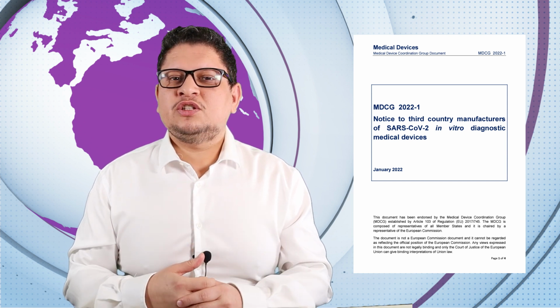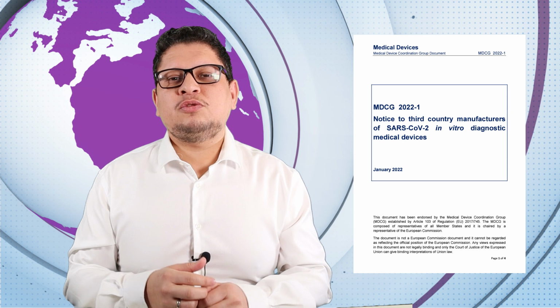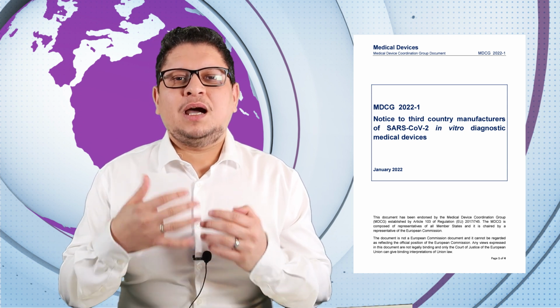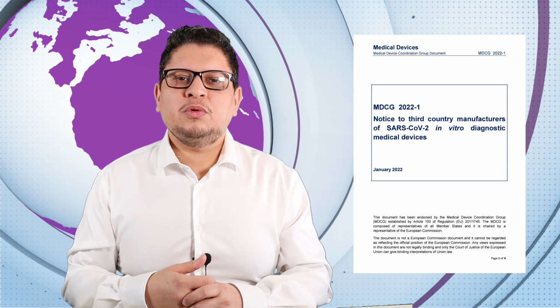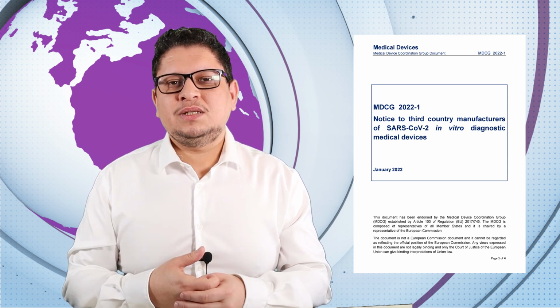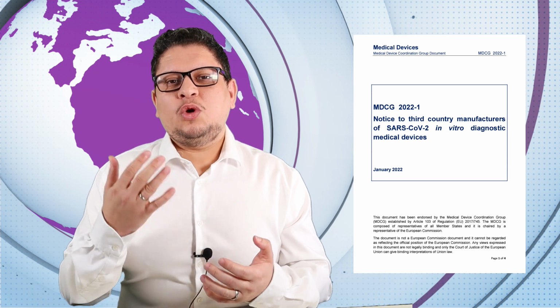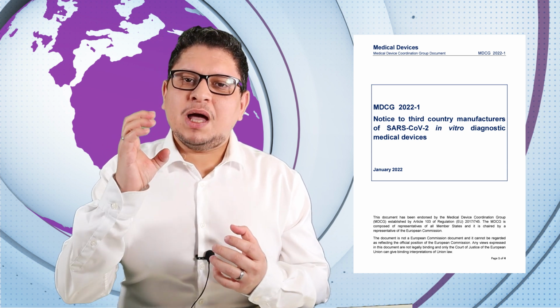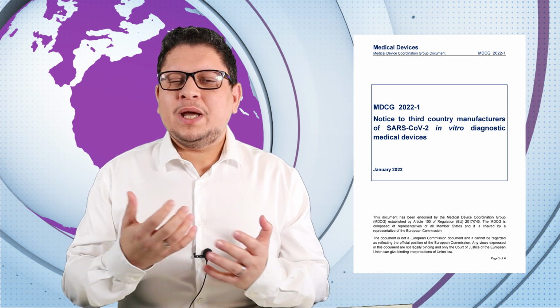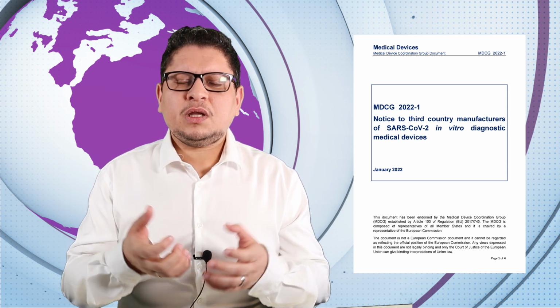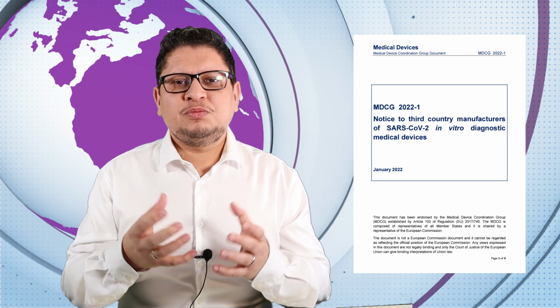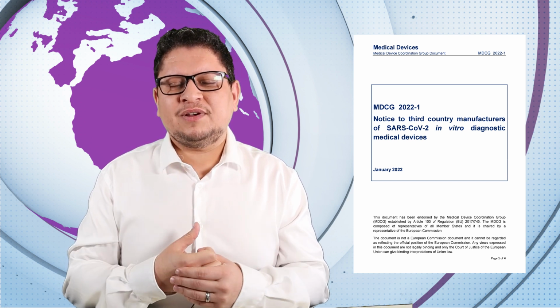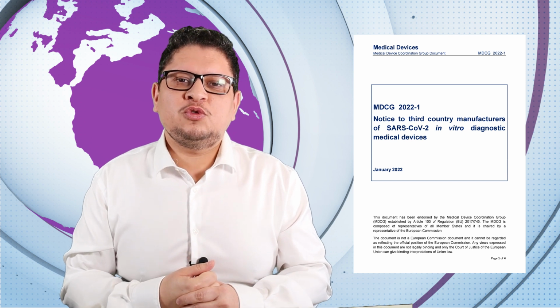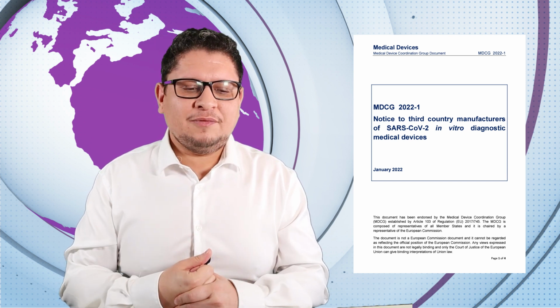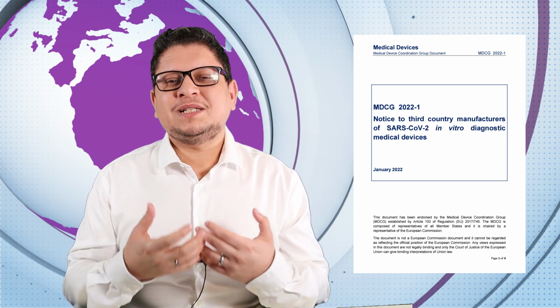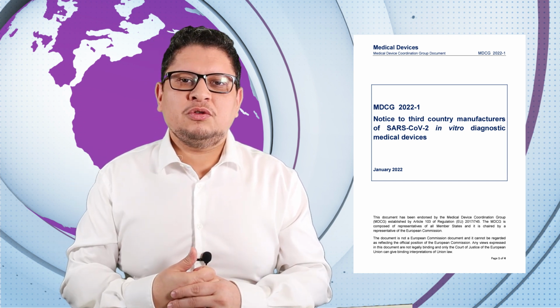The performance evaluation is not performed correctly. This is also important, and with the IVDR, we have more to do on that. So verify that your product is performing well. You also have to provide the performance on the IFU, the rate of sensitivity, everything to do with the product's performance should be written in the instructions for use. Don't forget to have that there, and to have the documents that prove all the information that you place in the instructions for use.